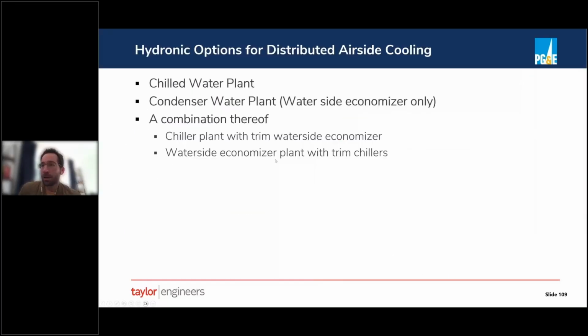So what are some of the hydronic options for serving these distributed air side systems? In contrast to some of the options that Jeff was going over, we can't tie an air side economizer onto an IRC, but we still want some form of economization to operate the data center more efficiently. So we typically might have a chilled water plant that has an integrated waterside economizer, or in some climates, we might just have what we'll call a condenser water plant, because we can get cool enough water using strictly economizing throughout the entirety of the year that we don't need chillers.